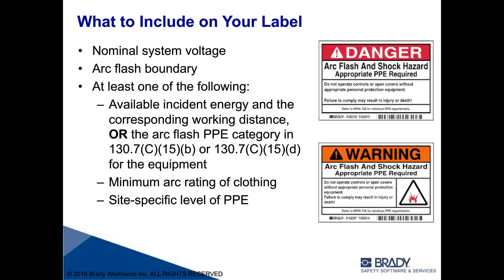The authors of the code realize that a lot of times those are both on there, and sometimes those can be conflicting in certain ways, but really the point is those two pieces of information are derived from two very different methods of calculation, or methods of arriving at that data. That available incident energy at the working distance, at 18 inches, is calculated based on the incident energy analysis method, which is having a consultant come out to the field, gather a bunch of data, and use software programs to do some calculations and figure out what that information is.